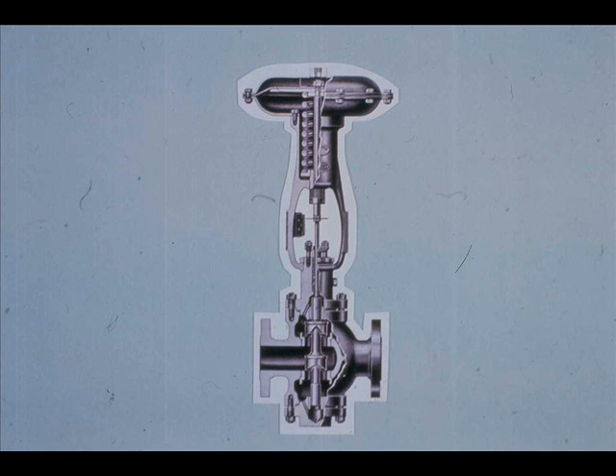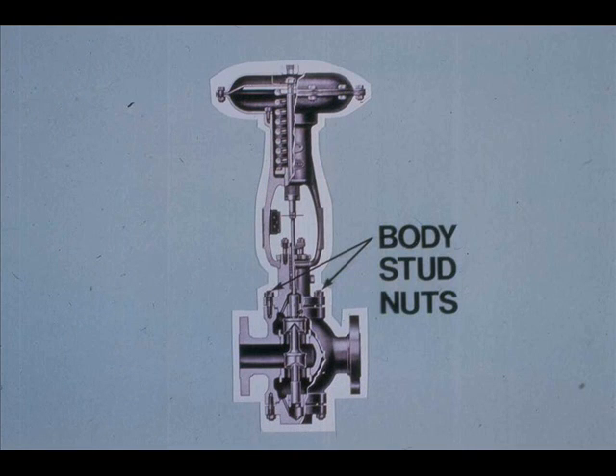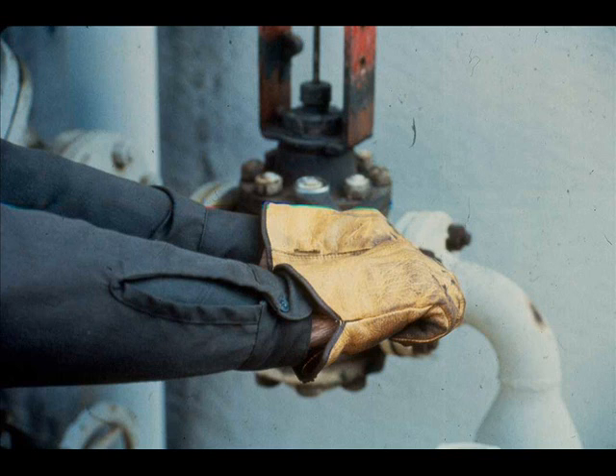The best way to repack a control valve is to remove all the old packing and add new packing. To remove all the old packing, you have to disassemble the valve. Look at the parts reference for a Masoneilan 10,000 series control valve and determine the best way to remove all the packing. Our valve is direct-acting, air-closed, just like this one. If you remove the body stud nuts, you can lift the bonnet off the valve body.